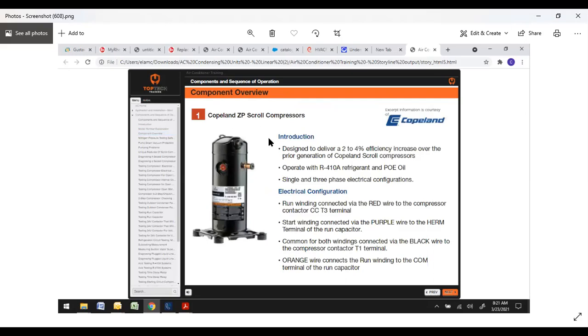Get your Copeland ZP compressor, designed to deliver 2 to 4% more efficiency over previous generations. Single and 3-phase configurations. Electrical configuration: the run winding is going to be your red wire. Start winding is going to be your purple. Your common is going to be your black. And your orange wire is going to connect your run winding to the common of your compressor.